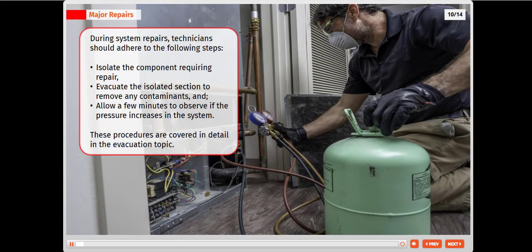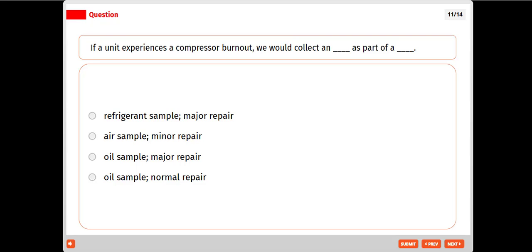During system repairs, technicians should adhere to the following steps. Isolate the component requiring repair, evacuate the isolated section to remove any contaminants, and allow a few minutes to observe if the pressure increases in the system. These procedures are covered in detail in the evacuation topic. If a unit experiences a compressor burnout, we would collect an oil sample as part of a major repair.